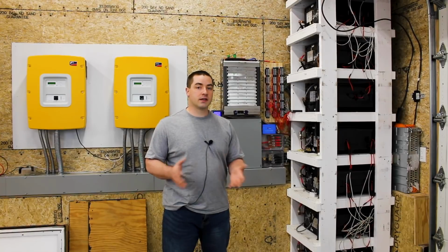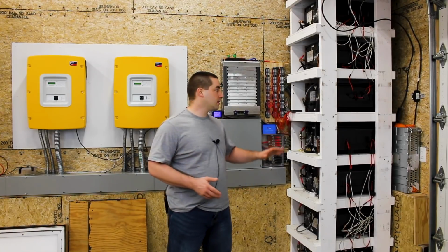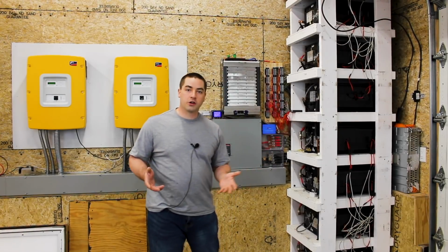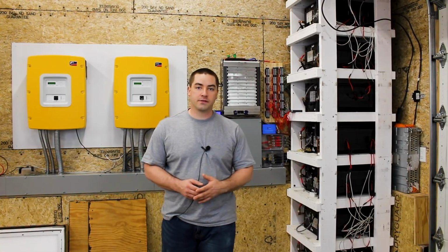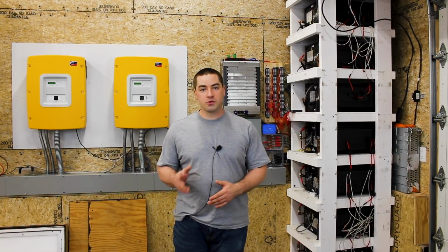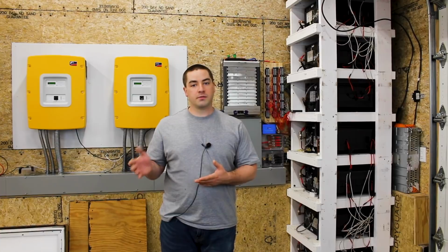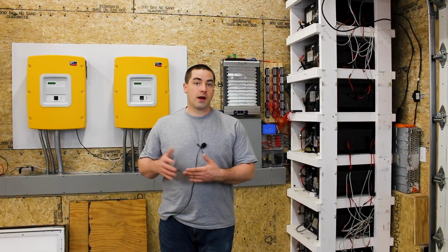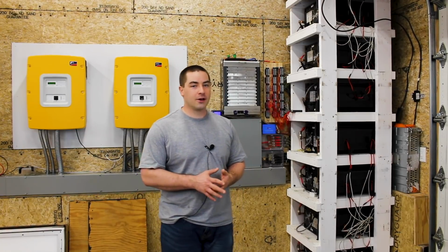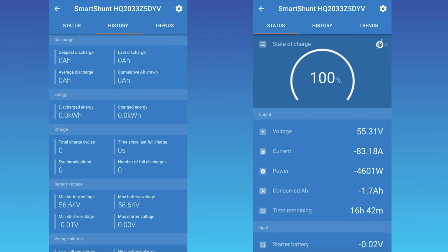Now today was a sunny day, and I allowed the whole battery bank to charge fully. It's at 100% state of charge. We sat in absorption mode until the absorption amps dropped down to 1 amp, so they are certainly at full voltage. I use a Victron charge controller on one of my solar arrays. That charge controller is set to 56.8 volts, that is the maximum voltage for the whole pack.